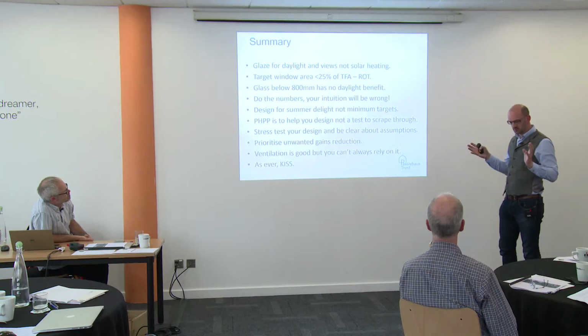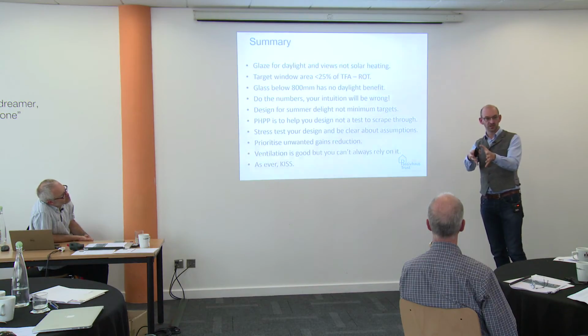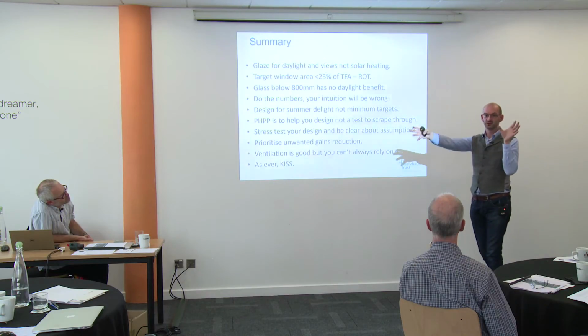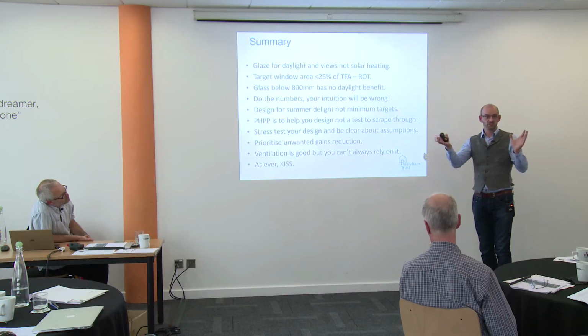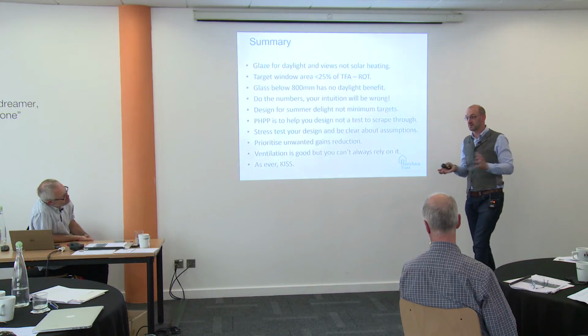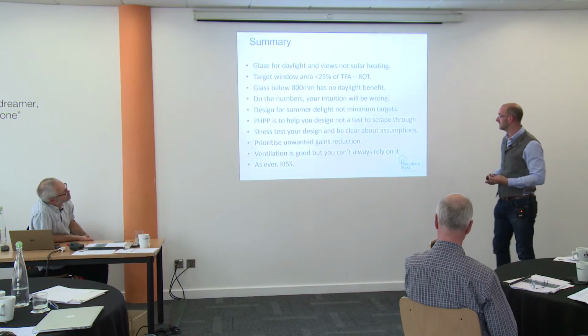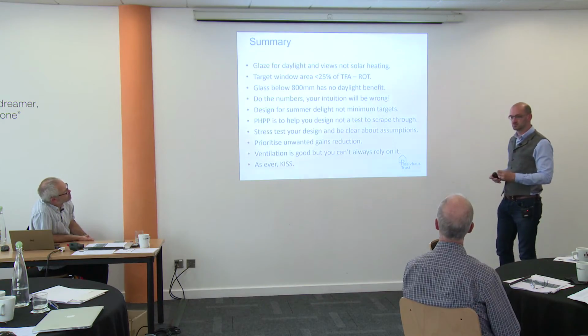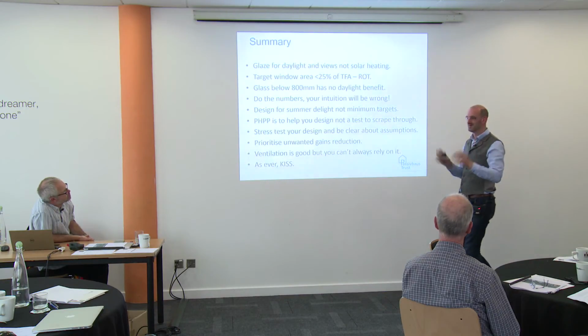One of the things I'd done at Steel Farm was looking at congregating all the glazing in one corner of the house, shall we say, or distributing it more evenly. The client preferred it to be more distributed because it had more of a traditional feel. In retrospect, that was definitely the right thing to do, because we avoided a lot of localised overheating issues that could have arisen. So sometimes you don't need a PHPP to tell you that if you distribute the glass evenly, it'll be less of a problem.